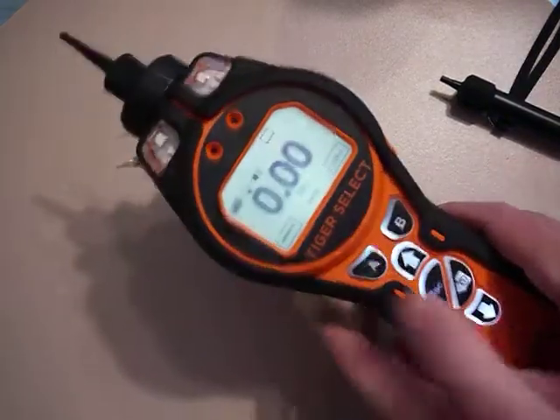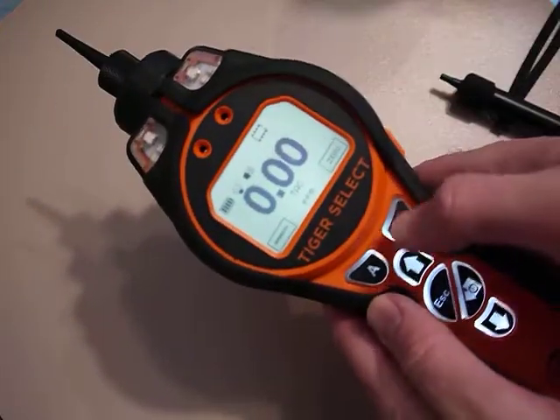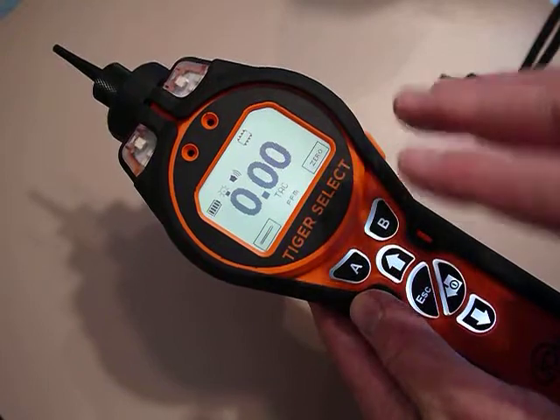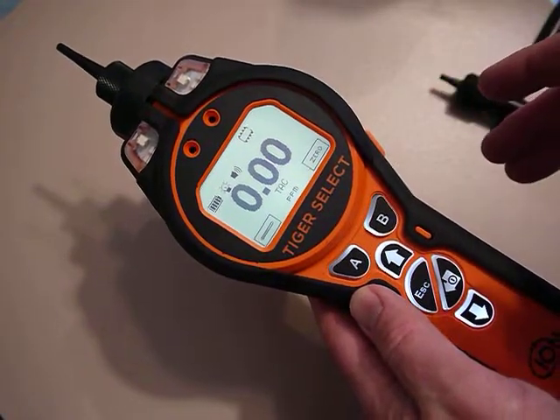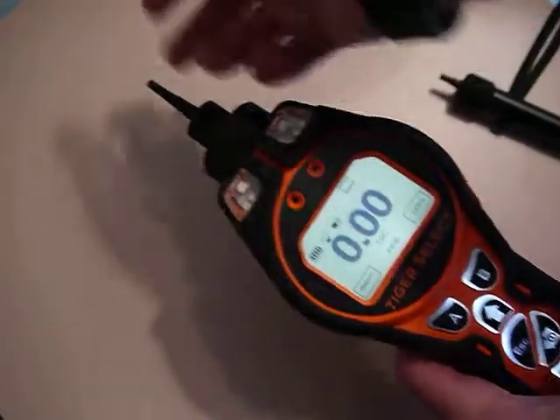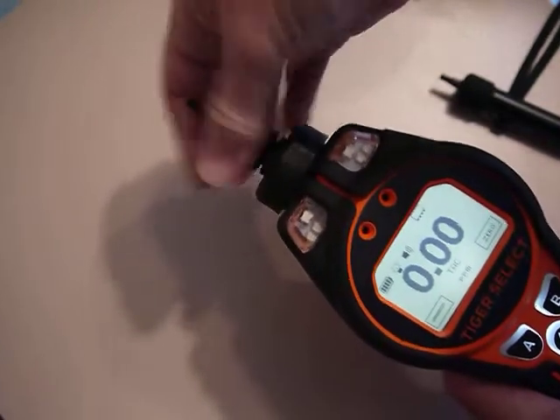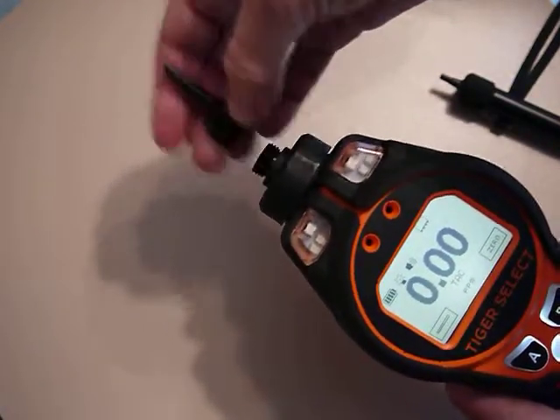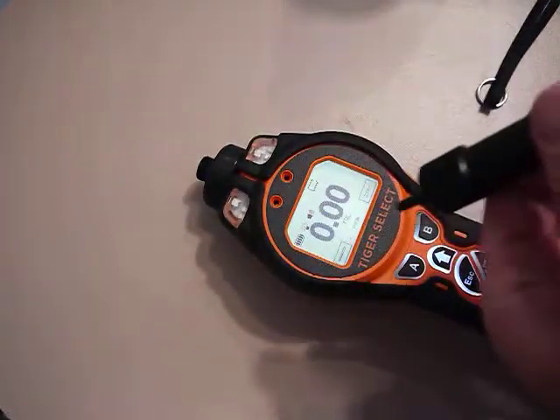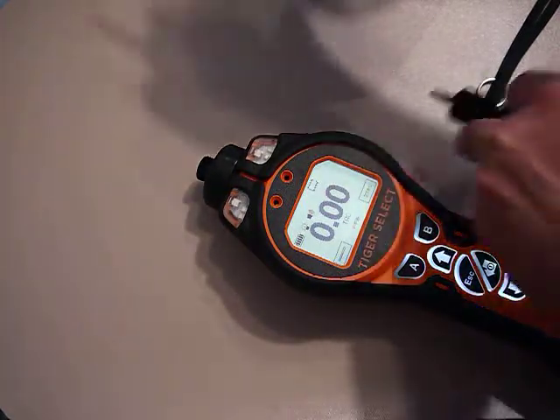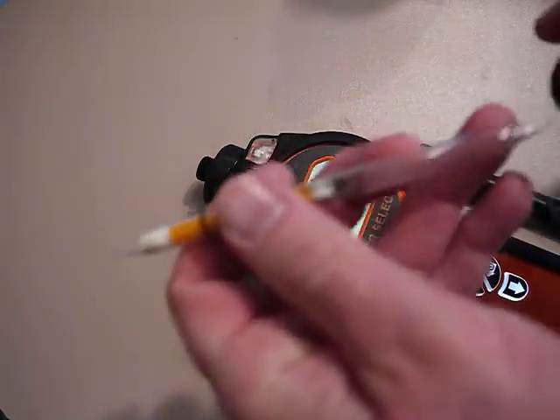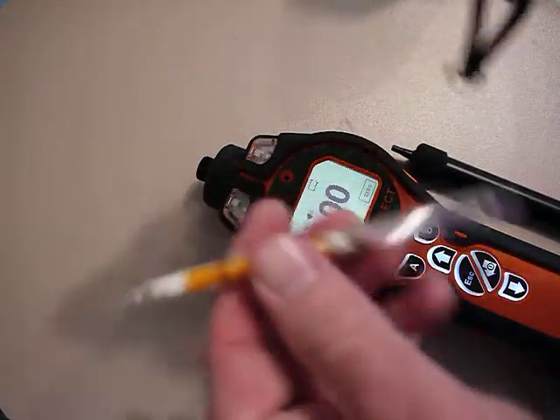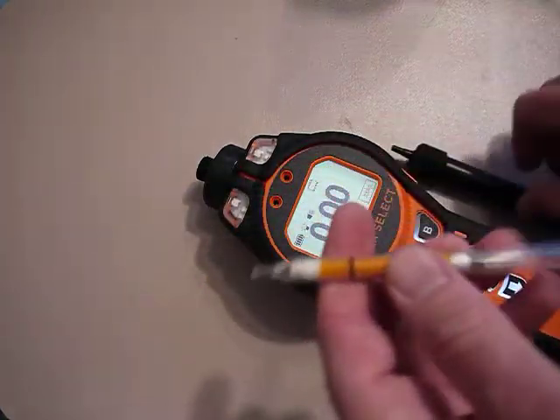So what I would do now is let the unit run for at least 15 minutes to stabilize, and while it's doing that I can take this end off. Now I've already done this, I've already broken a tube, but basically you take a tube, put it into this tube breaker, move it around, snap the ends off, and then you carefully take in the tube.